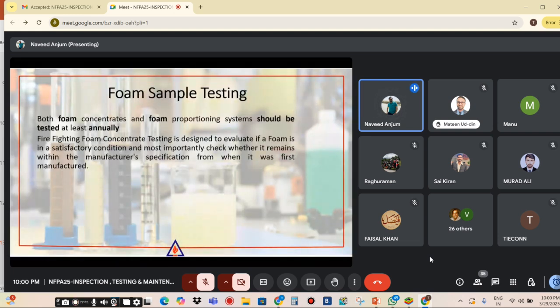Foam testing. Mostly there is also an issue during my visits. I have seen that mostly industry is not doing foam sample testing. It is also mandatory to check your foam system annually. Firstly, you have to do foam quality testing. You cannot assume from its physical appearance, like seeing a lot of bubbles, that it will extinguish the fire. No, it cannot be assumed. We have to check in the laboratory whether it has the total performance to extinguish the fire or not. So we have to test it completely.